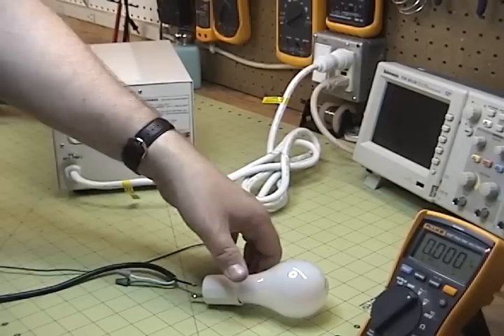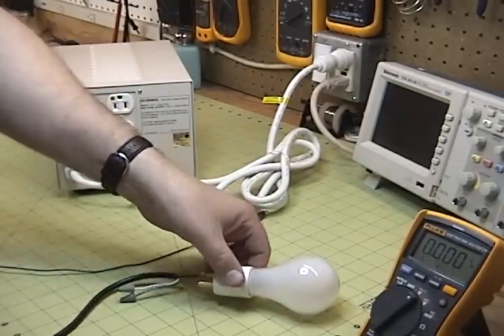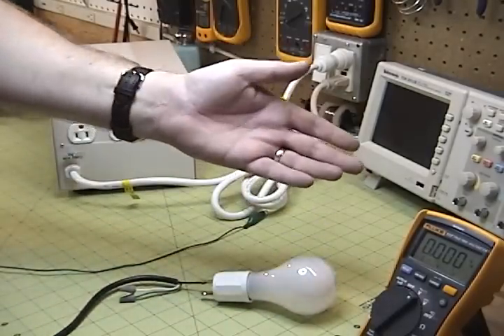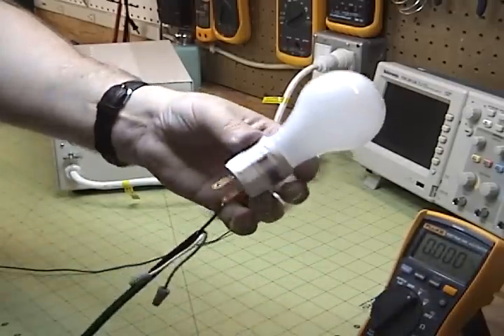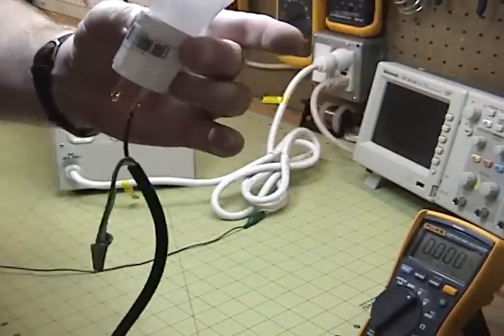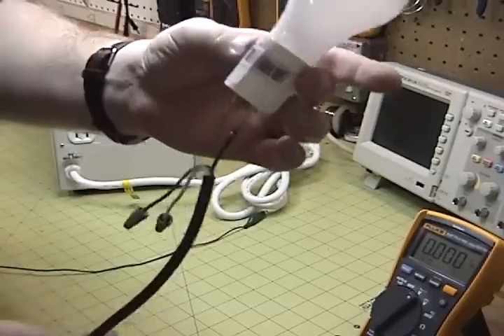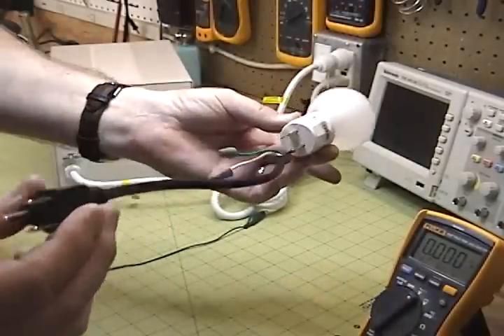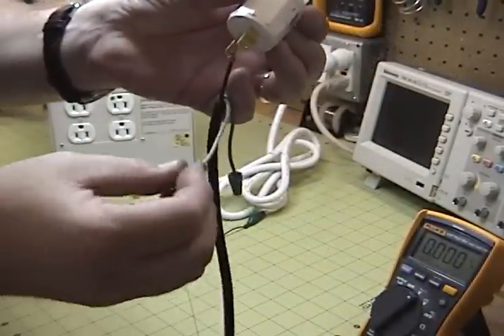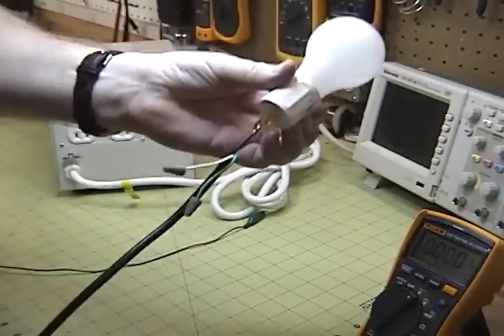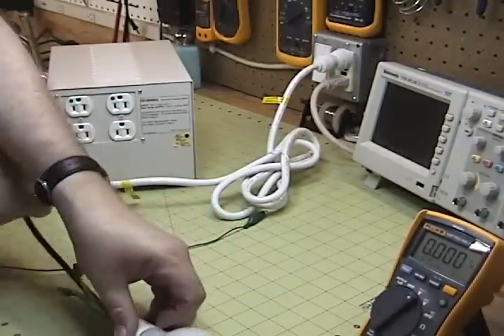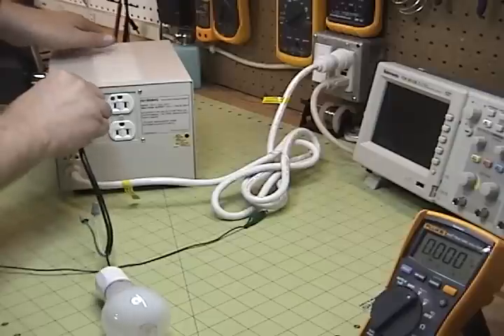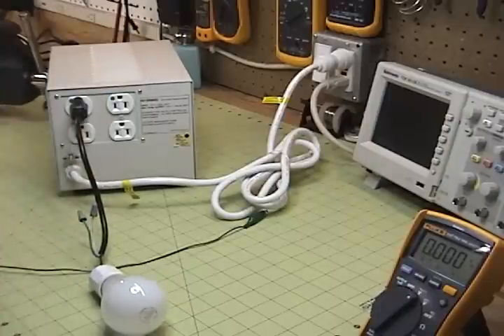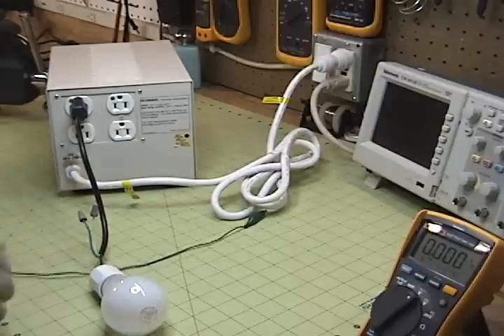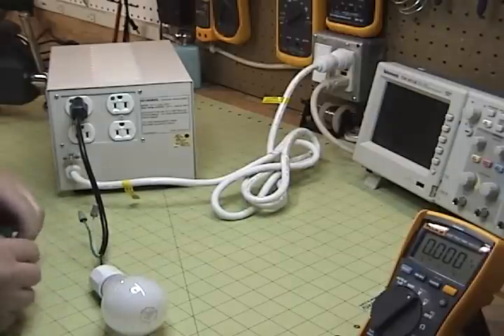This test shows that voltage is actually able to provide current, not just a high voltage with infinite resistance. I've got a light bulb with one leg hooked to the hot side of an outlet cord, a little short outlet cord, without the second leg, the white or the ground, hooked up. Then I'm going to plug that into my transformer. It's still an unaltered factory transformer with that secondary strap to ground for common noise rejection.